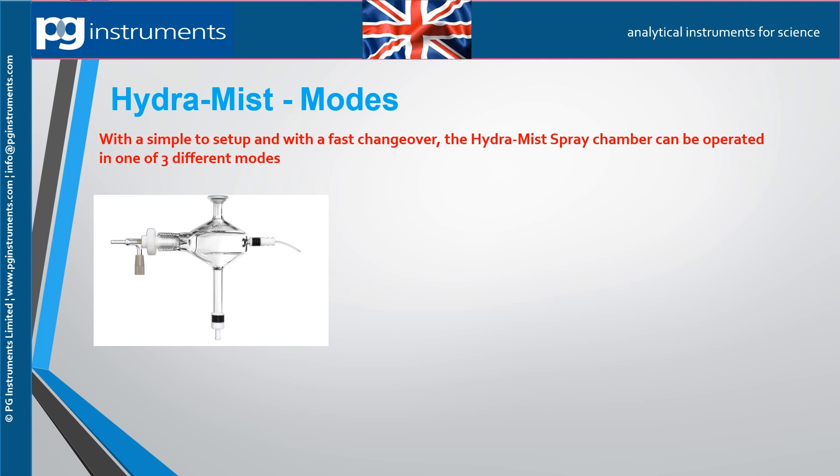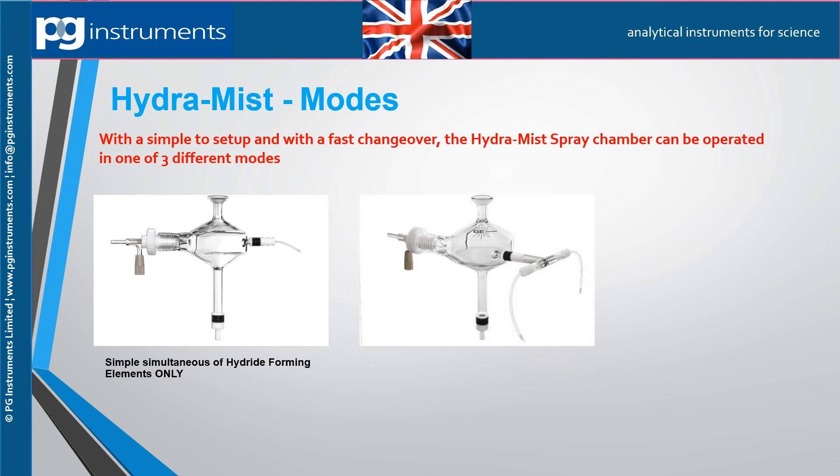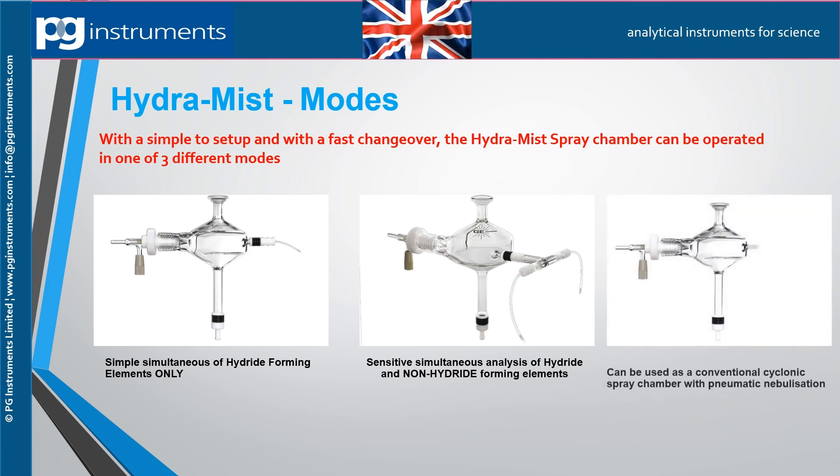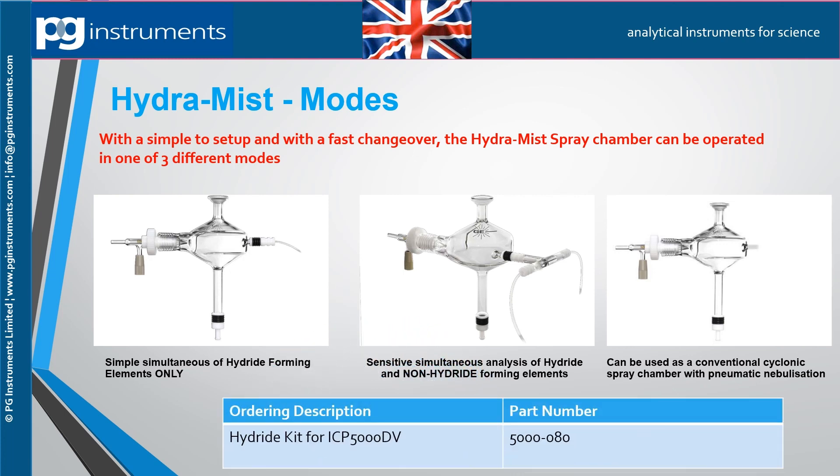The Hydra-Mist system can be used in three ways: firstly, for simultaneous analysis of hydride forming elements such as arsenic, selenium, antimony, and mercury; secondly, and most importantly, for sensitive simultaneous analysis of hydride and non-hydride forming elements; and thirdly, as a conventional cyclonic spray chamber with pneumatic nebulization for general analysis.